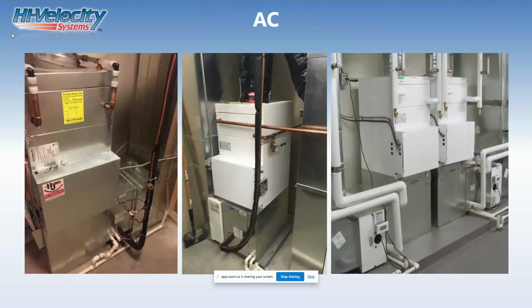So again, heat pumps work on cooling coils. You must have a cooling coil. Our cooling coils go on the return air side of our air handlers, and the refrigerant gets forced backwards if it's in a heating cycle, or the proper way if it's in a cooling cycle. So you must have an air conditioning coil. Now, our air conditioning coil is heat pump ready. It's got an adjustable TXV ready to go, accepting a heat pump application. And it's the same footprint as a fan coil. So again, compact. Our fan coil's compact. That's what you're seeing right there: our fan coil with a cooling coil underneath and ductwork on it.